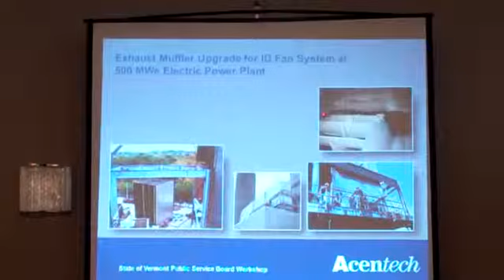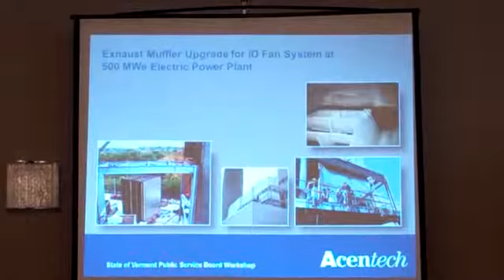In that case, we specified a tuned dissipative silencer. This is a silencer that has some special baffles within it that are tuned to the different frequencies of interest, the 150 hertz and 300 hertz tones. It was quite effective, and that one was also solved.